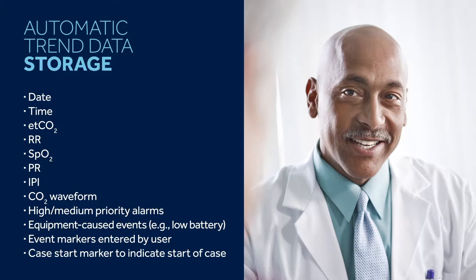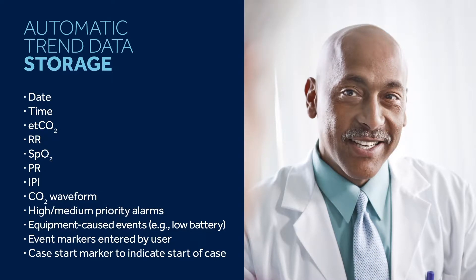Trend data is stored automatically for 48 hours of monitored time. However, data is cleared when you admit a new patient and select Remove Previous Patient Data. CO2 waveform data is saved 20 times per second. All other data is saved once per second.